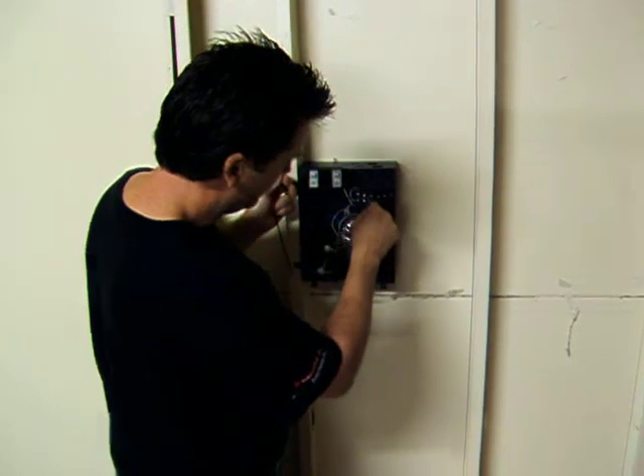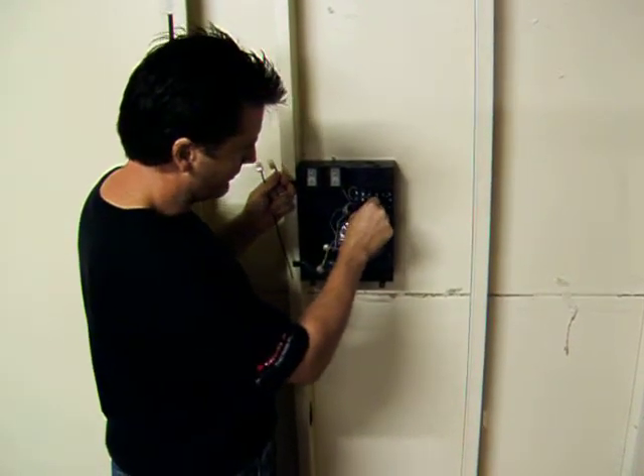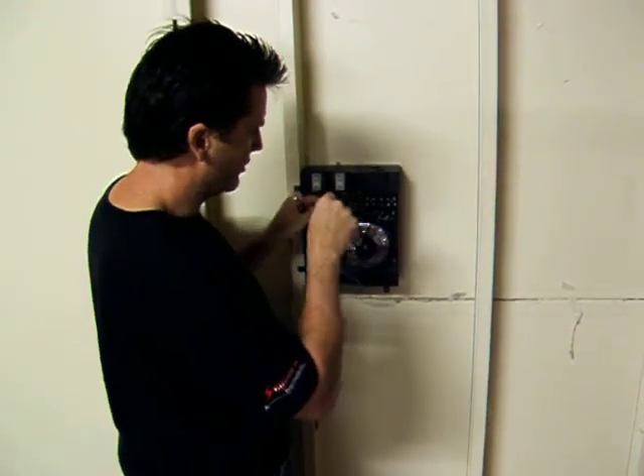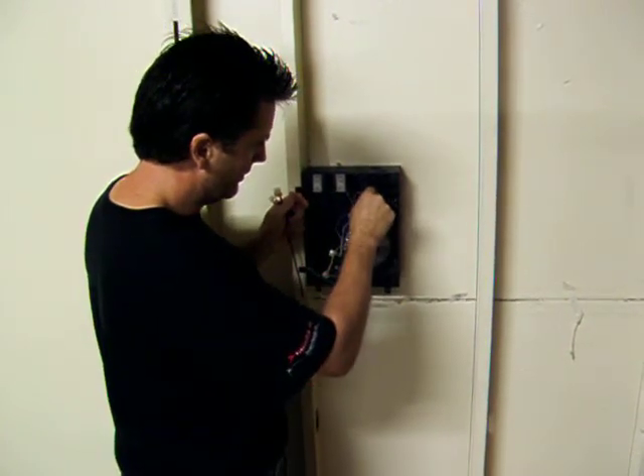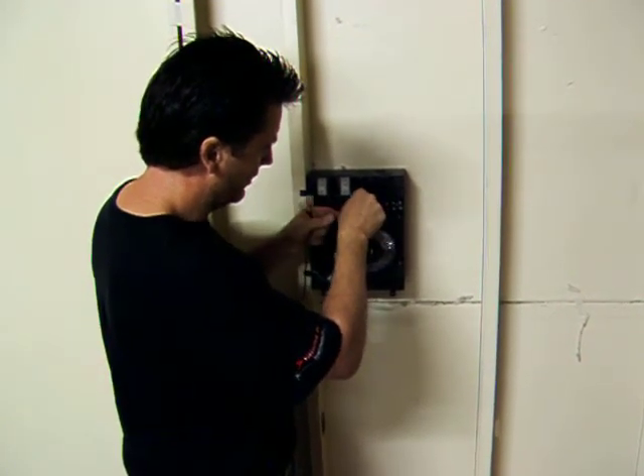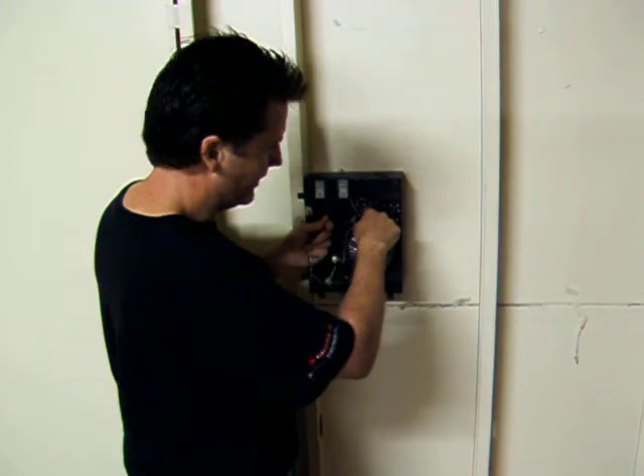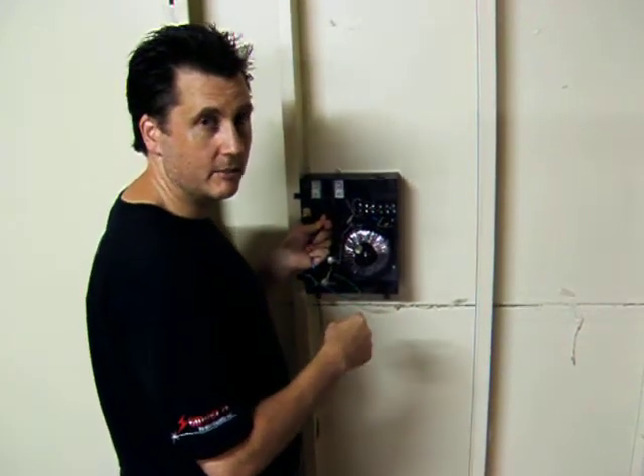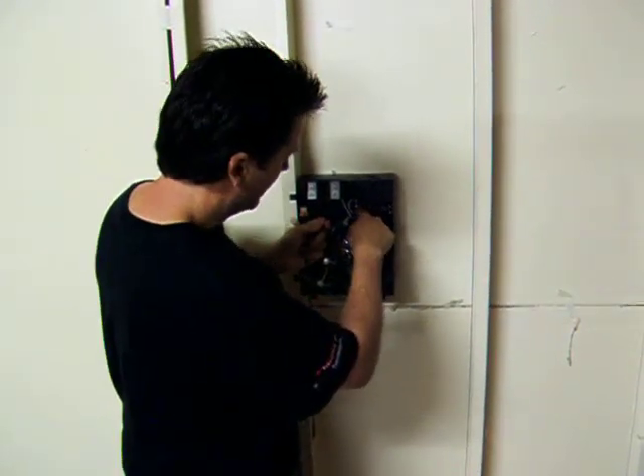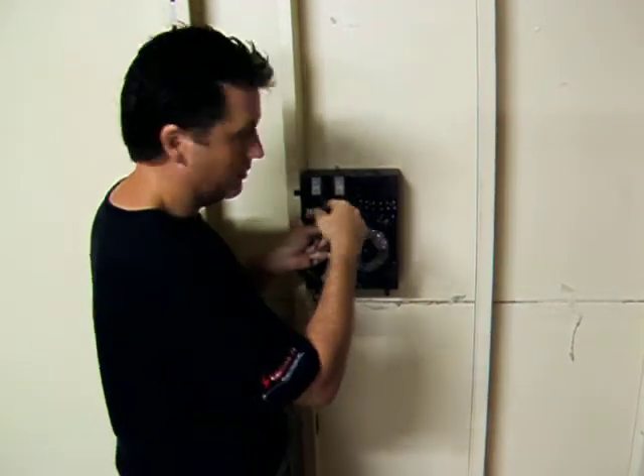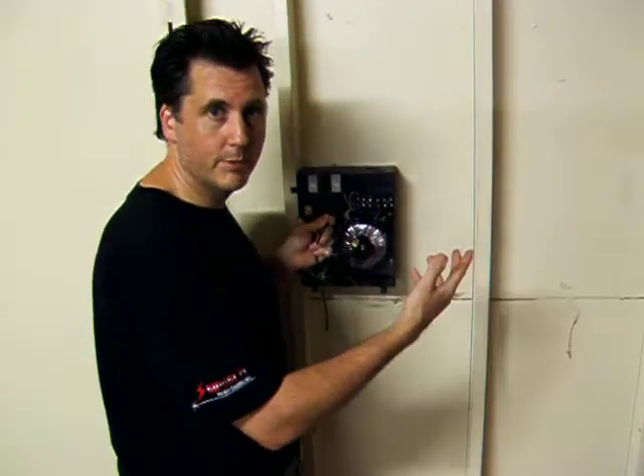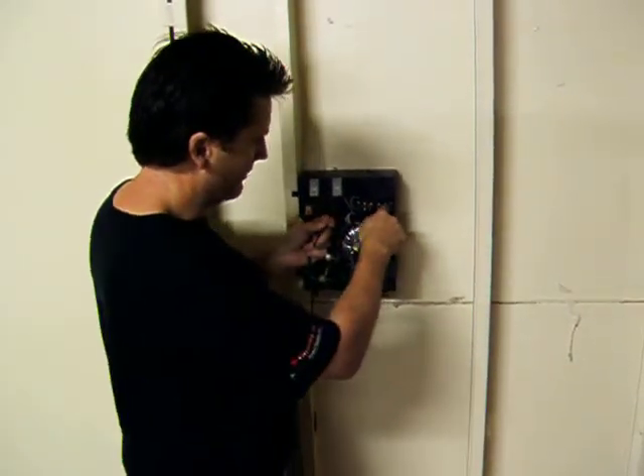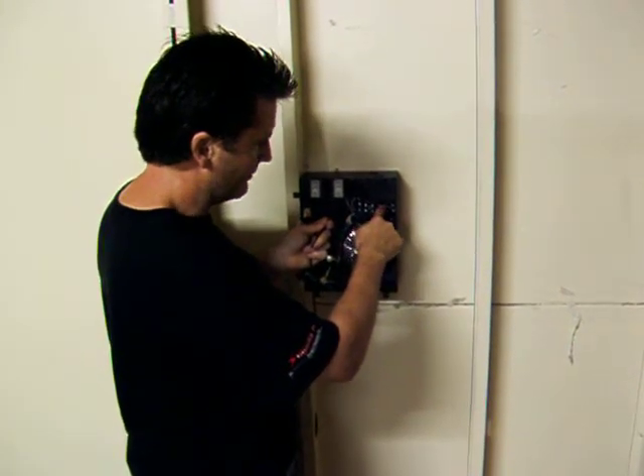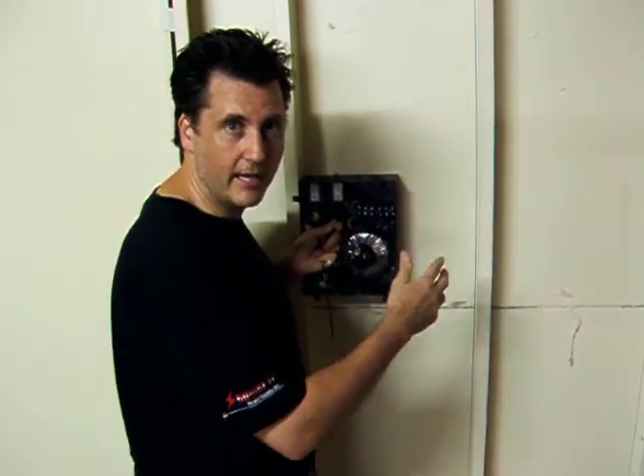Now the other end, you'll notice, there are 5 different taps. If you're not sure which one you need, you plug into the very first tap. So you'd put it under the terminal block and you'd tighten it down to 16 pounds. And then if you measure your voltage and you need to boost it, you would put it into a higher tap. Each one of these taps will raise it approximately a half a volt.